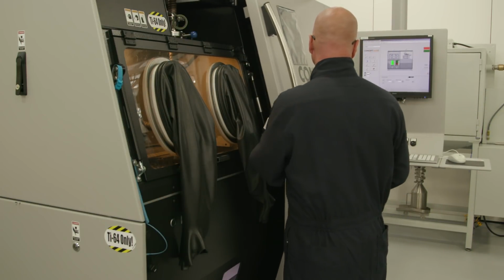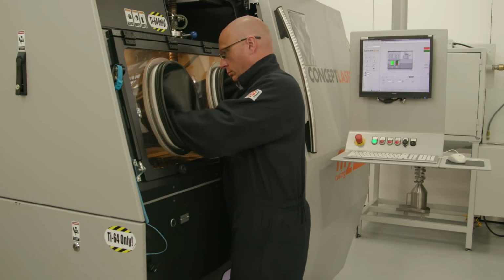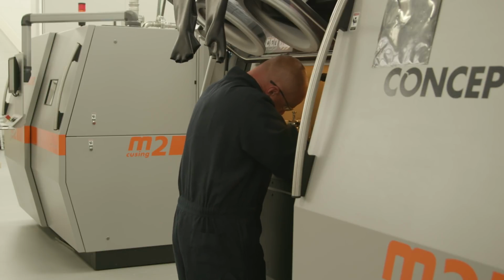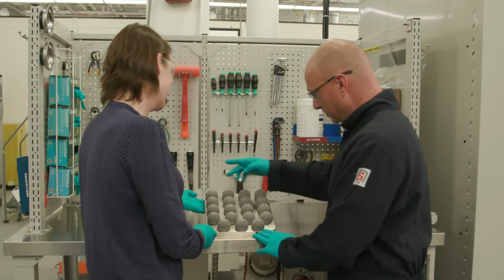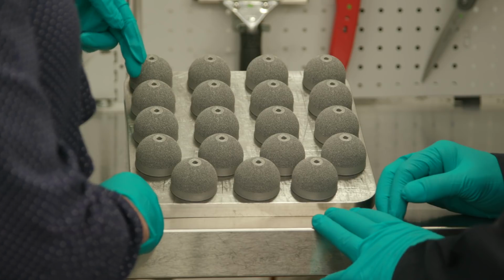At many points, Stryker engineers had to develop their own know-how. Early on especially, few industry-wide technical standards were available. If you're actually creating your standards and you have to create the performance standards for the product, that we're pretty good at. But consistency and looking at all the unknowns of additive manufacturing, for instance, when you have a build plate and you're making 10 different parts in one run, are all the parts based on location of the build plate exactly the same? What is the difference? If you look at different powder configurations, lot by lot by lot of material powder, were we creating the same part? When you made parts, did you have some areas where maybe the consolidation of the powder wasn't as great as you wanted and you had some porosity?